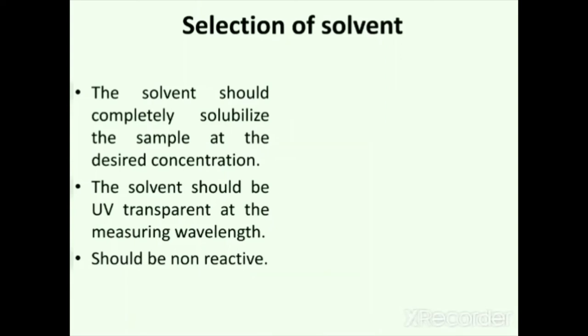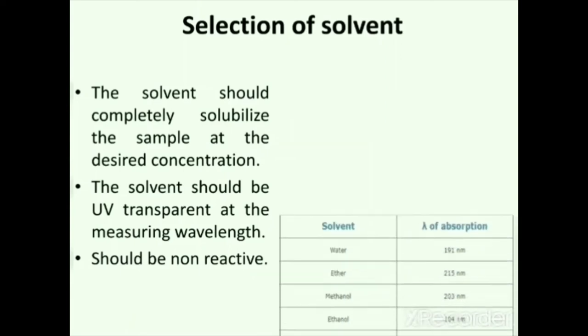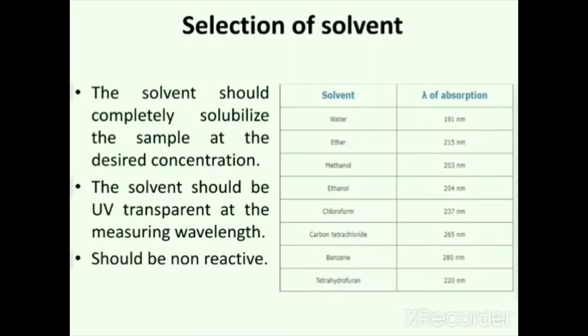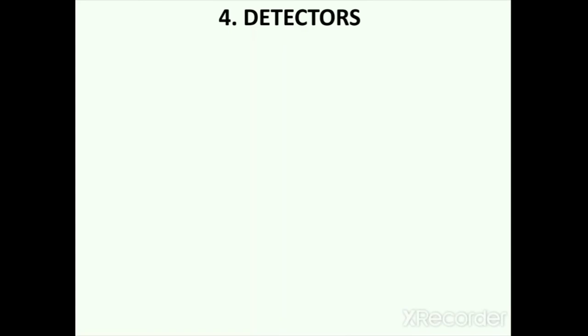Common solvents and their UV absorption cutoff wavelengths are: water at 191 nm, diethyl ether at 215 nm, methanol at 203 nm, ethanol at 204 nm, chloroform at 237 nm, carbon tetrachloride at 265 nm, benzene at 280 nm, and tetrahydrofuran at 220 nm.